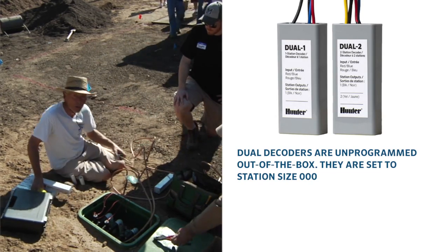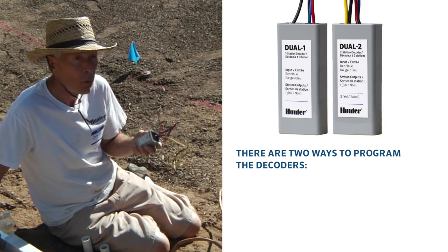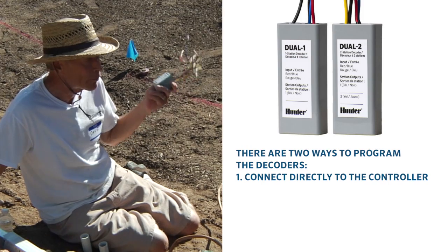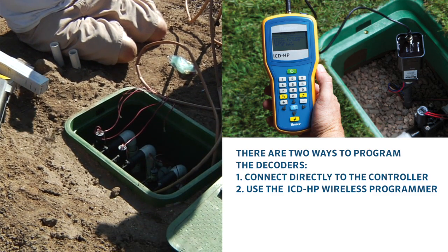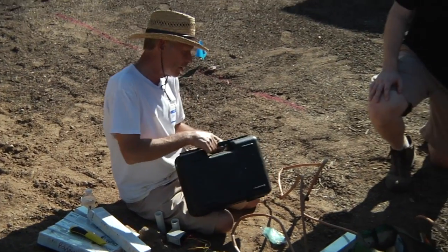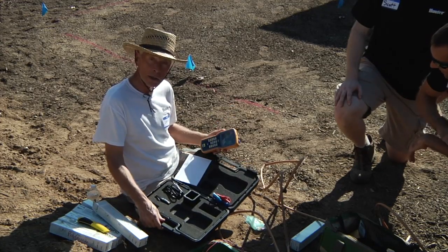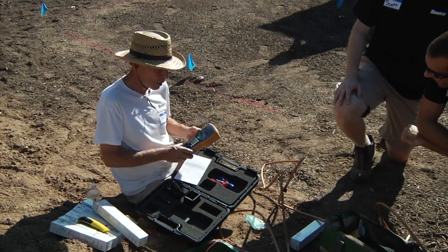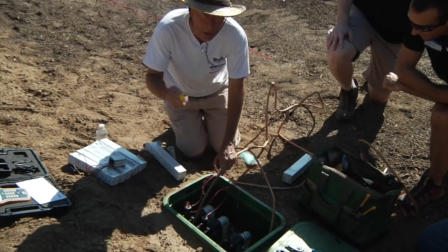One other thing — these decoders are unprogrammed out of the box, set to station zero-zero-zero, so we need to program them and we need power to do that. There are two ways: one is to hook them up right to the controller in the garage, but you can also use our slick handheld device — the ICD-HP wireless programmer — which is battery-operated and will supply power during the programming process. We'll see this in action a little bit later. The ICD-HP is the greatest thing that ever happened to the decoder business.